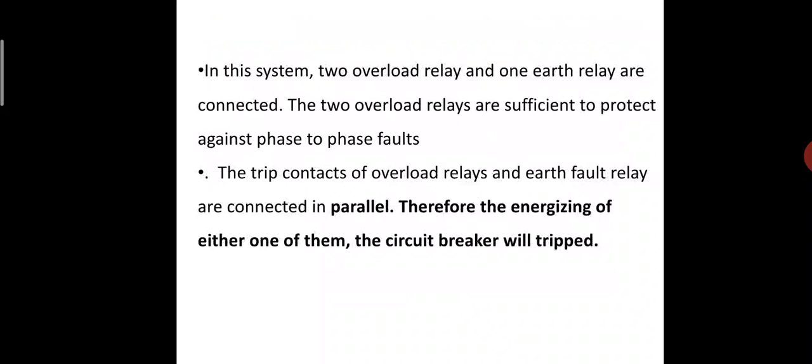In this system, two overload relays and one earth relay are connected. The two overload relays are sufficient to protect against phase to phase faults.